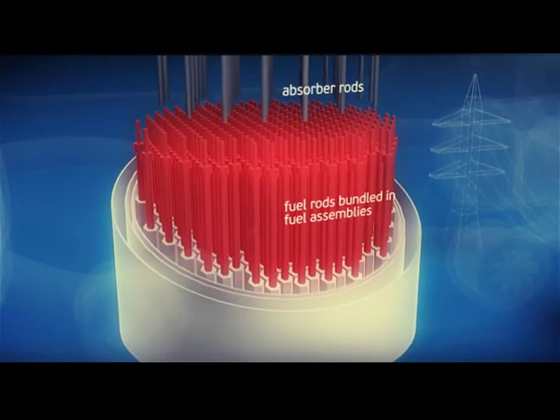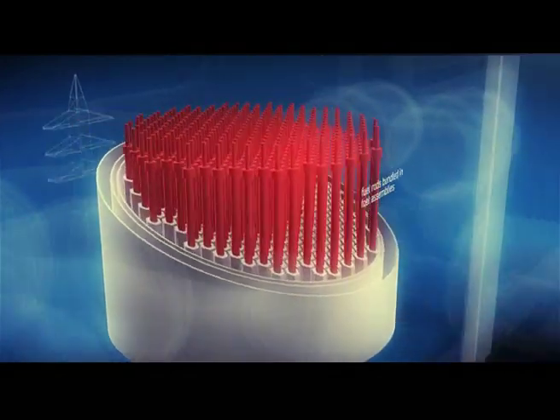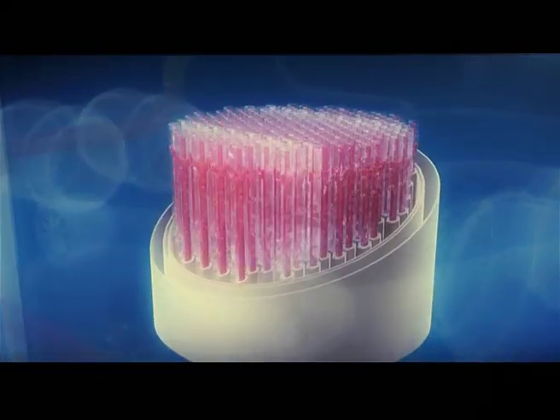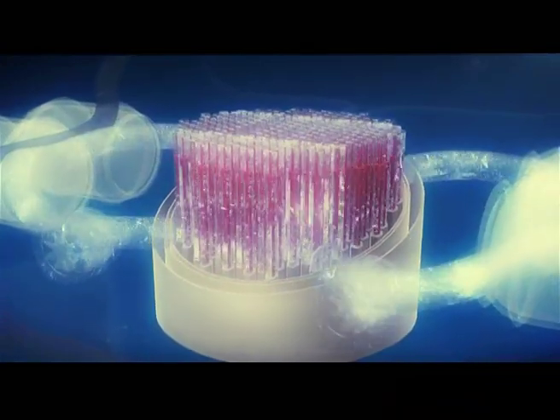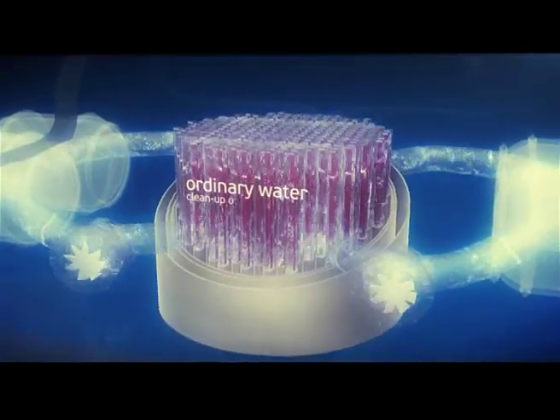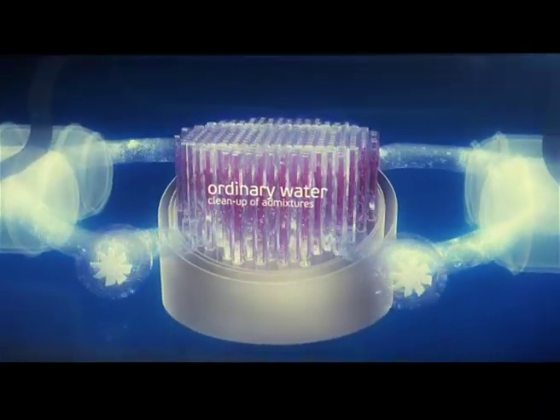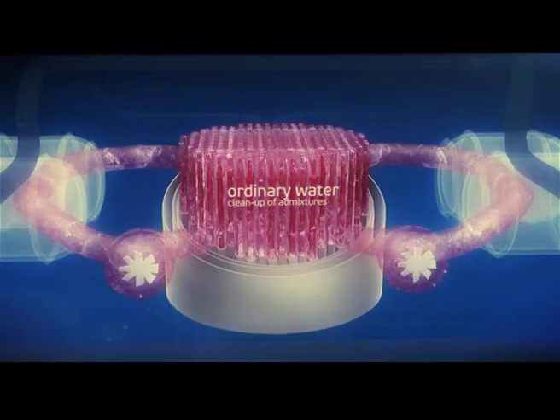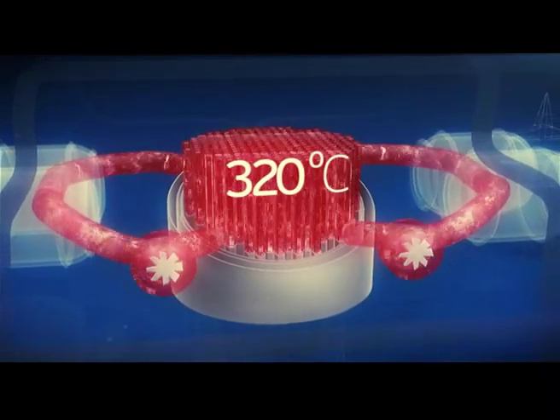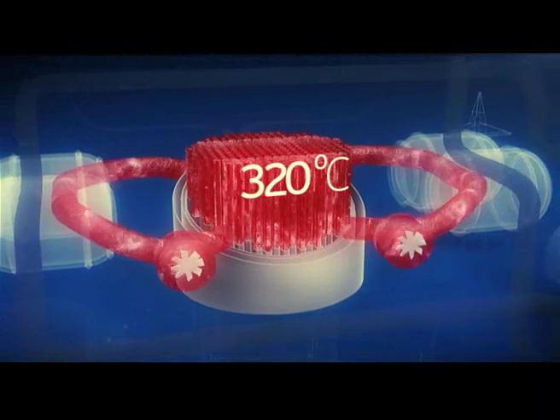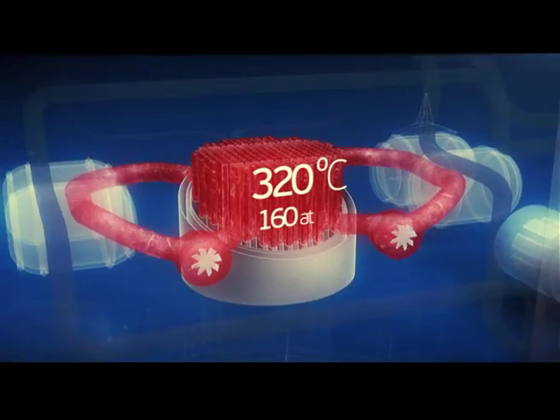Nuclear power plants with VVER reactors employ a two-loop arrangement. Ordinary water, cleaned from all admixtures, circulates through the reactor. When passing through the core and washing over the fuel rods, it is heated up to 320 degrees Celsius. To keep it in liquid state, it has to be under a pressure of 160 atmospheres.